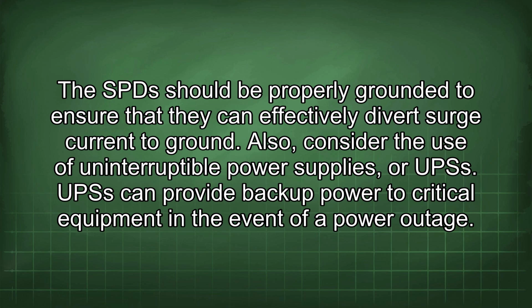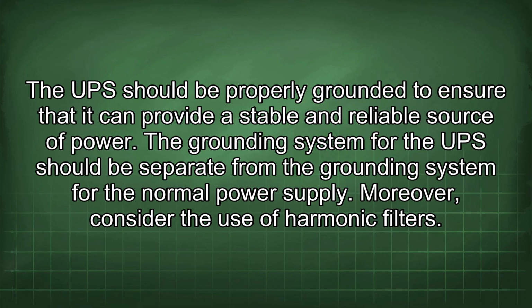Also, consider the use of uninterruptible power supplies, or UPSs. UPSs can provide backup power to critical equipment in the event of a power outage. The UPS should be properly grounded to ensure that it can provide a stable and reliable source of power. The grounding system for the UPS should be separate from the grounding system for the normal power supply.